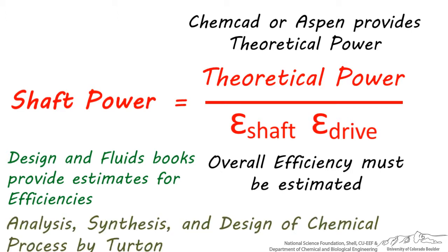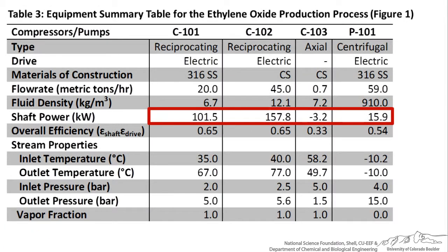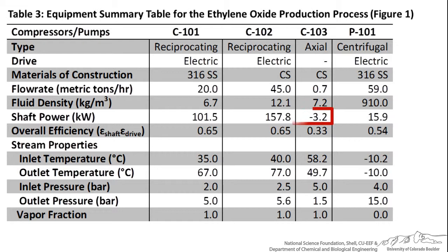Once you've estimated the shaft and drive efficiencies, you can calculate overall efficiency, which then gives us shaft power. Notice that C103 has a negative shaft power, because this is a turbine and not a compressor. Energy is removed from the fluid instead of being added to it, so the sign is negative.